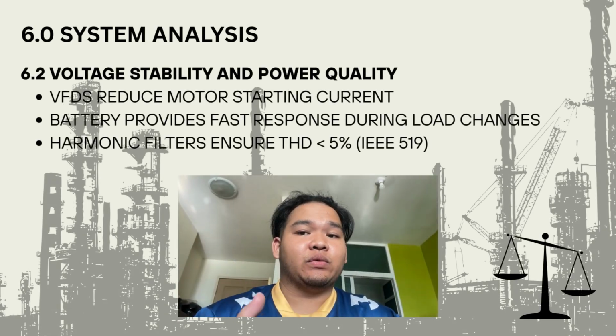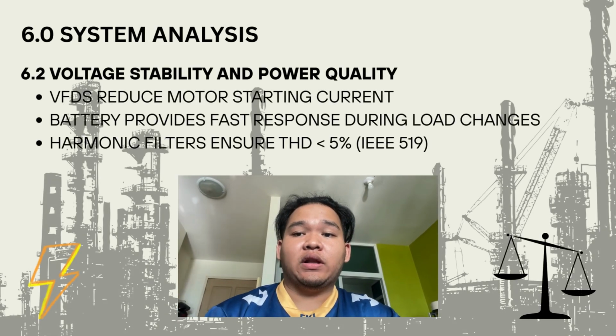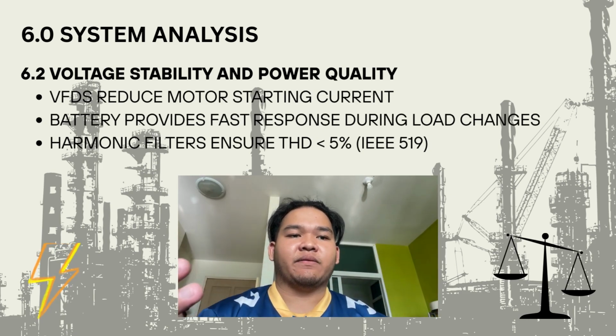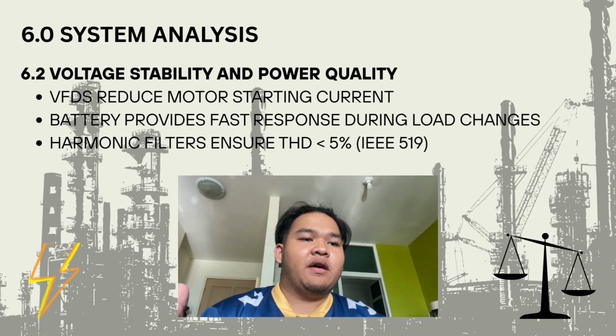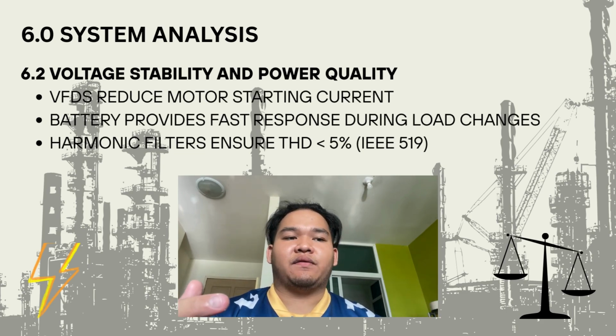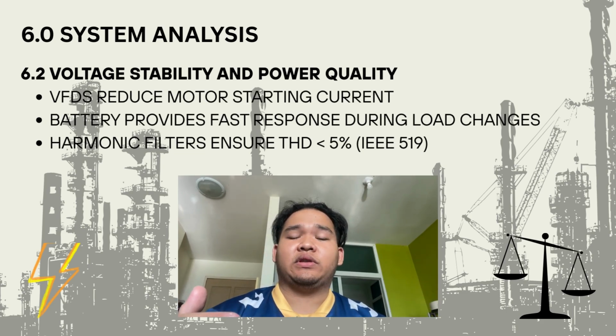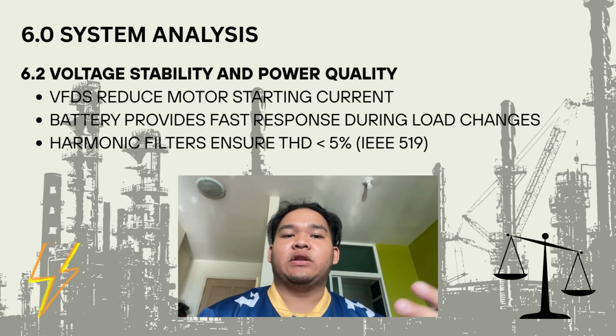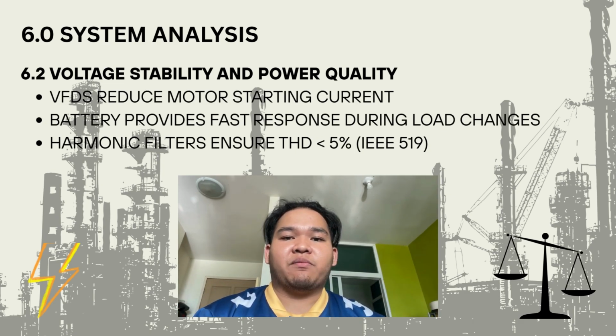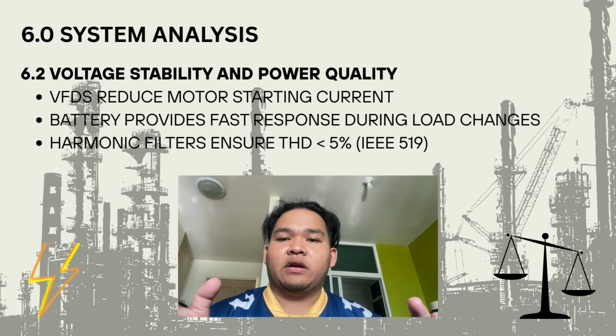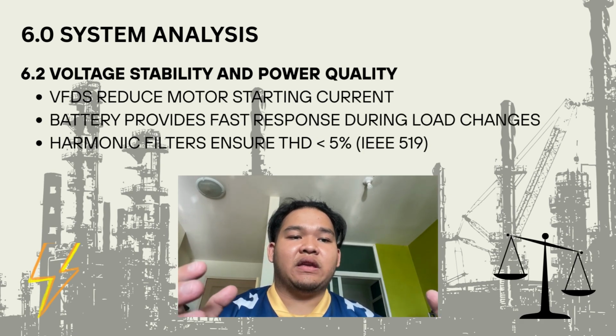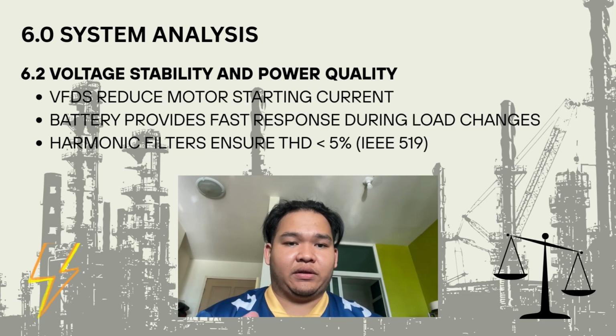Now, 6.2, voltage stability and power quality. Because this is an off-grid system, voltage stability is very important. Variable frequency drives, known as VFDs, are used to reduce motor starting current and prevent voltage drops during startup. The battery system provides fast support during load changes. Harmonic filters in the inverter and VFDs ensure that harmonic distortion remains below 5% in compliance with IEEE 519 standards.